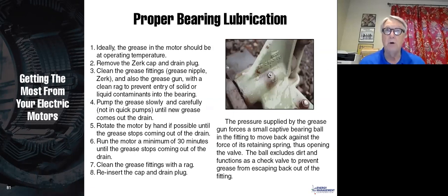Who greases motors? Well, sometimes you have really good quality, smart people that grease motors. But I would say that too often the guy who greases the motor is the new guy. Why? Because nobody wants to grease motors. It's not a fun job. And so the new guy does it, and the new guy doesn't know how. You get improper greasing, and you have premature motor failure. One of the most important things you can do in your facility is to have a proper bearing lubrication program.